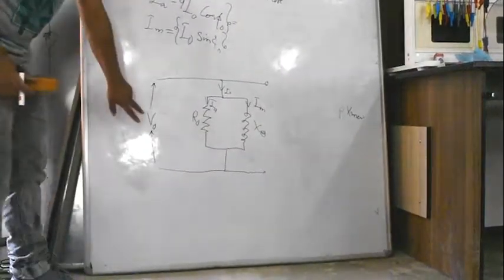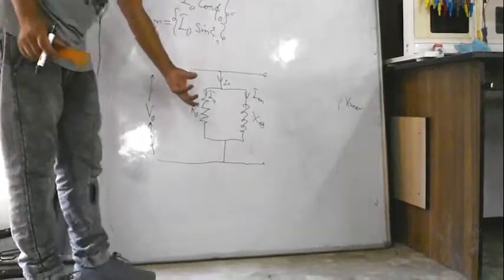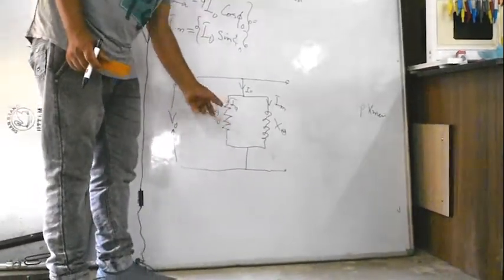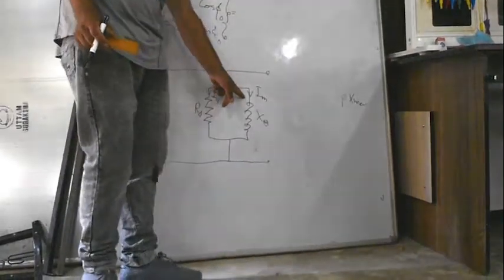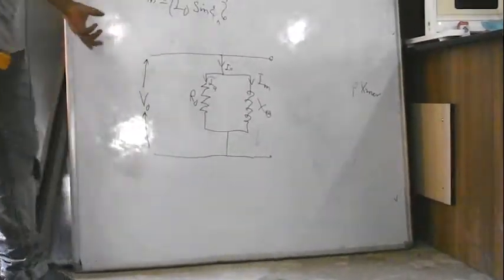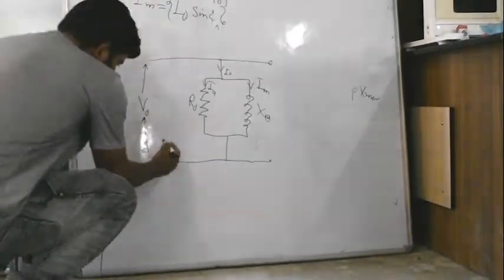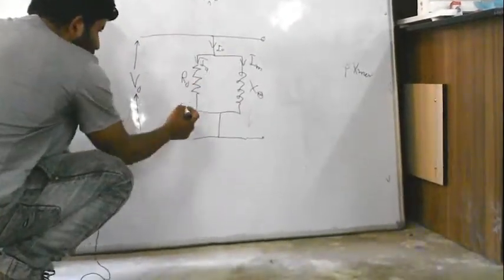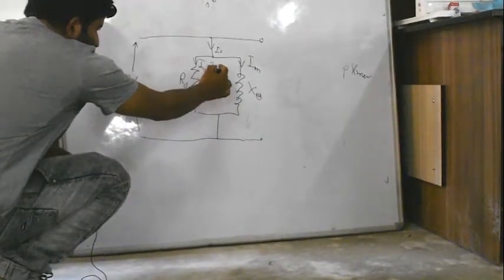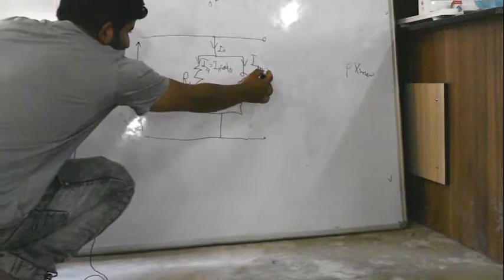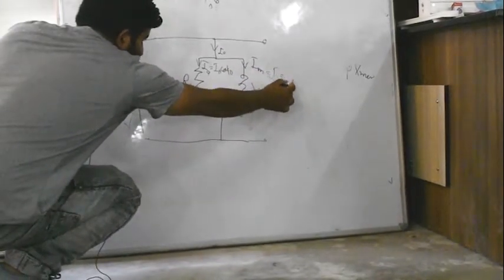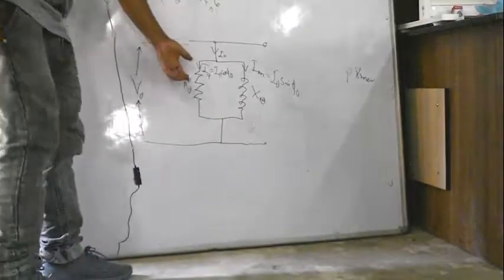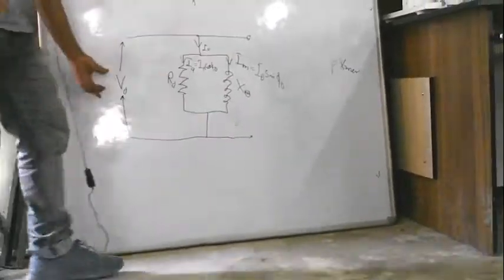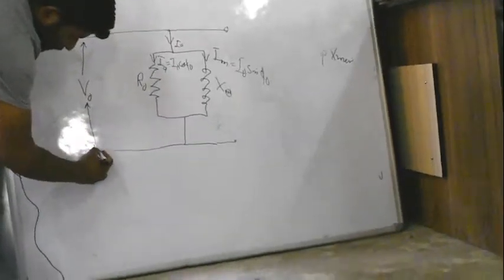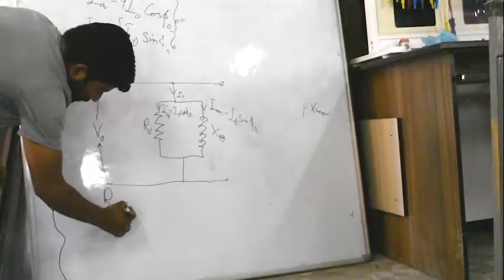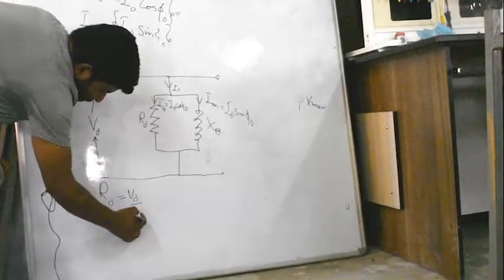So, you have this reading V naught, you have the magnitude of this active component of current, and you have the magnitude of this magnetizing component of no load current. Both are connected in parallel across this V naught. So you can easily obtain, because this Ia is I naught cos phi naught in magnitude, and this Im is I naught sine phi naught. So, knowing the value of this current and knowing the value of this voltage, you can obtain these two: the resistance R naught in ohms will be simply V naught by Ia.